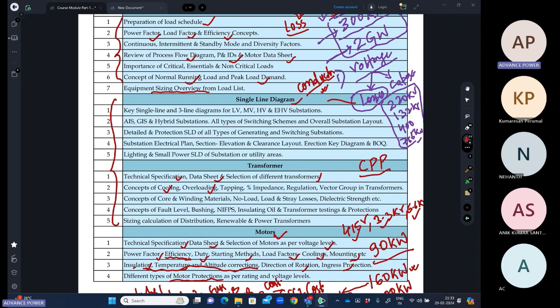So if I am talking about the solar transmission transformer, generator transformer, so different overloading will be there. So solar transformer will be having a cyclic duty nature. It will be having an overloading for suppose 2 to 3 hours only. So we'll discuss as per IEC 60076 part 5, and I will discuss with the IS 6600 also. So overloading concept will be clear to you, that what overload you can do with your transformer. So different transformer which is running for different application can be overloaded differently.